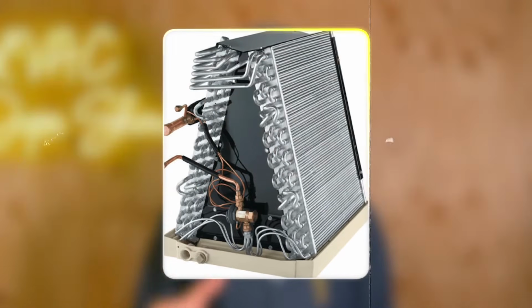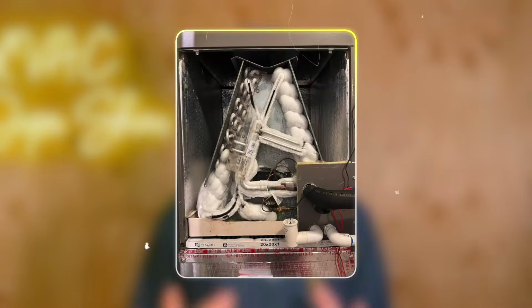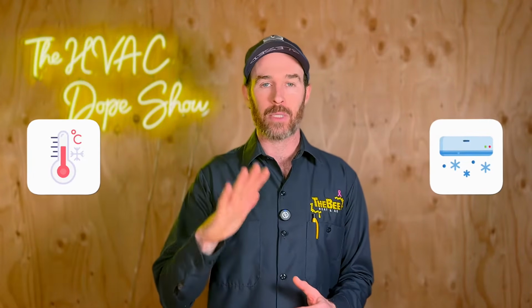But the reason that an evaporator coil or your indoor coil will start to ice up if it's getting not enough airflow is because the temperature of that refrigerant is getting below freezing. And so the moisture that would normally be coming off of that coil in the form of condensation instead starts to freeze as soon as the temperature of that coil gets below 32 degrees Fahrenheit.